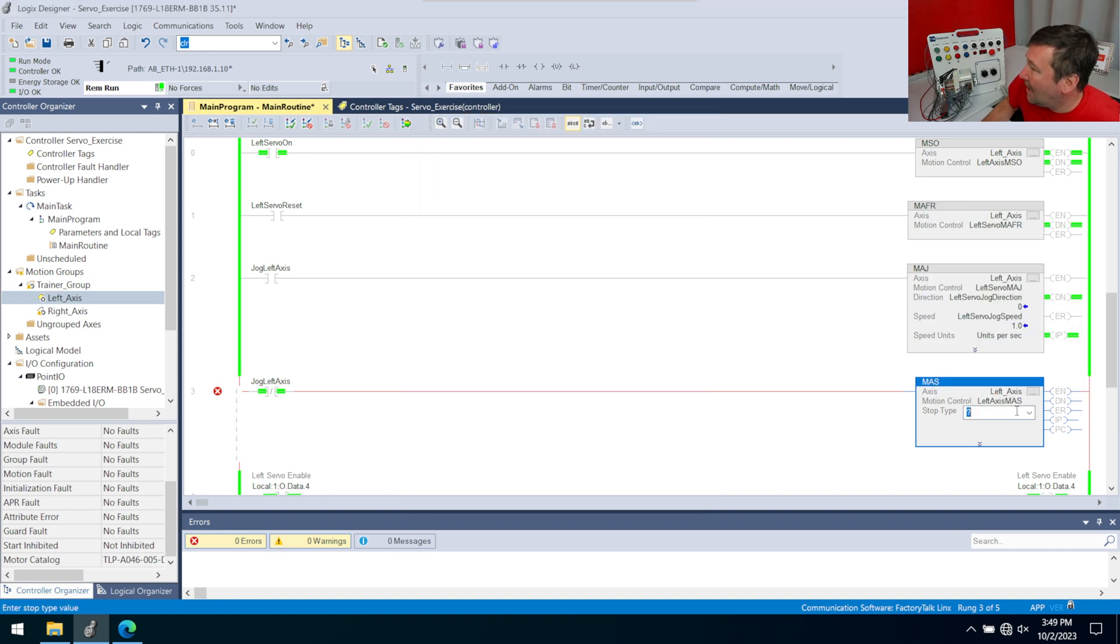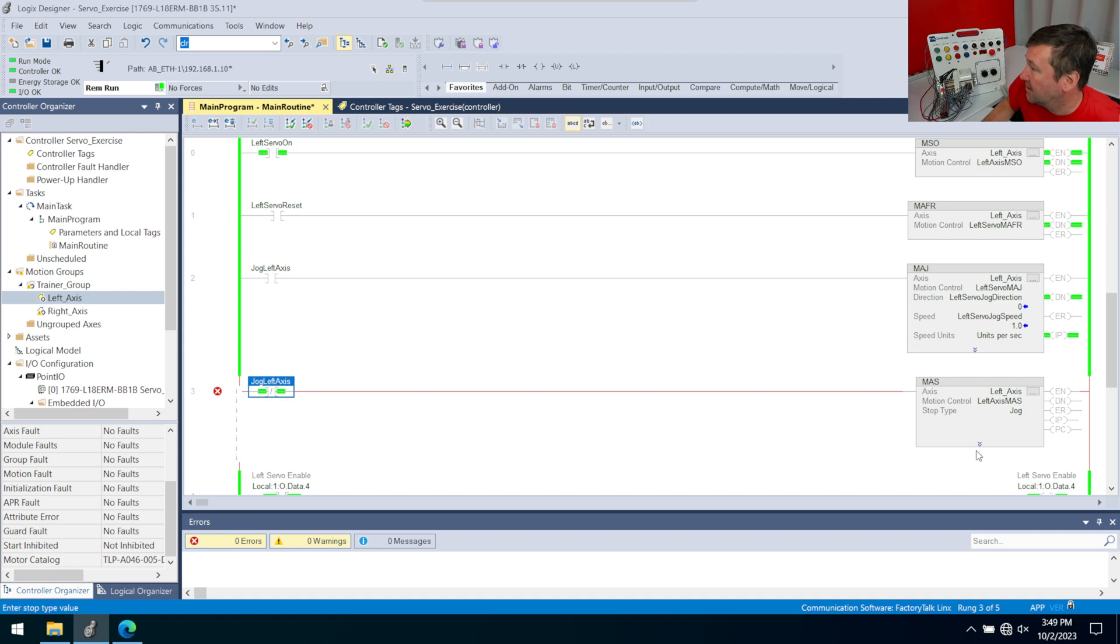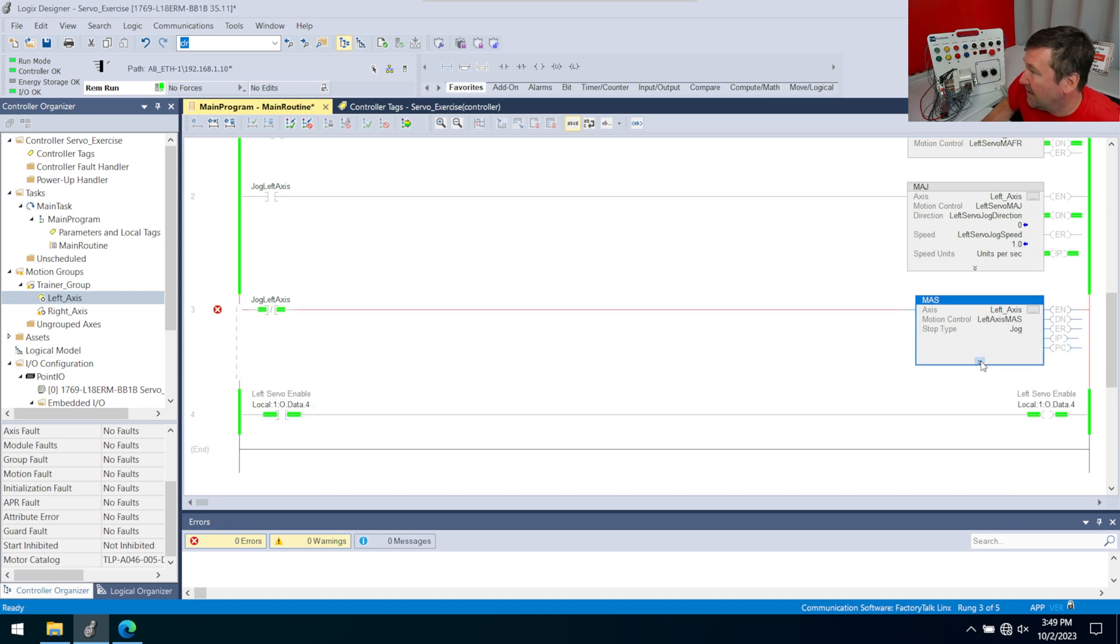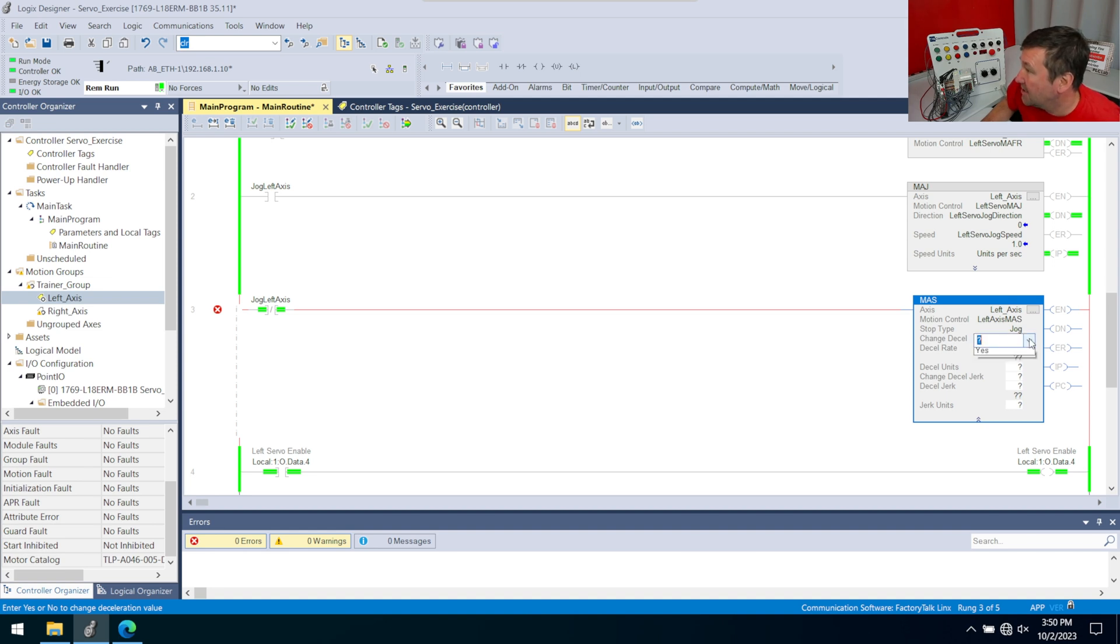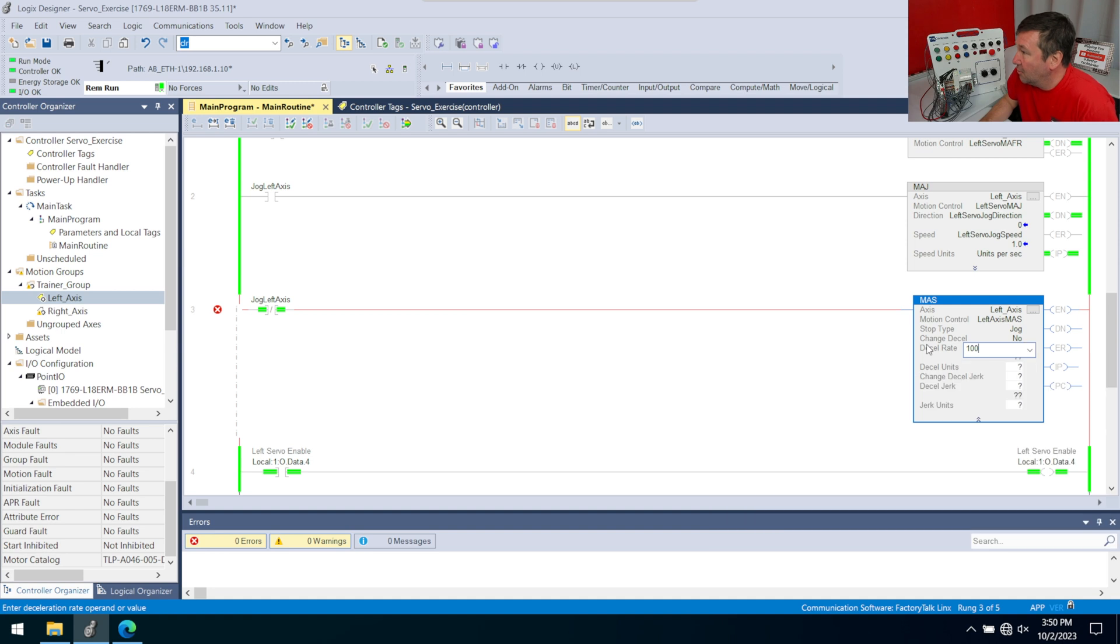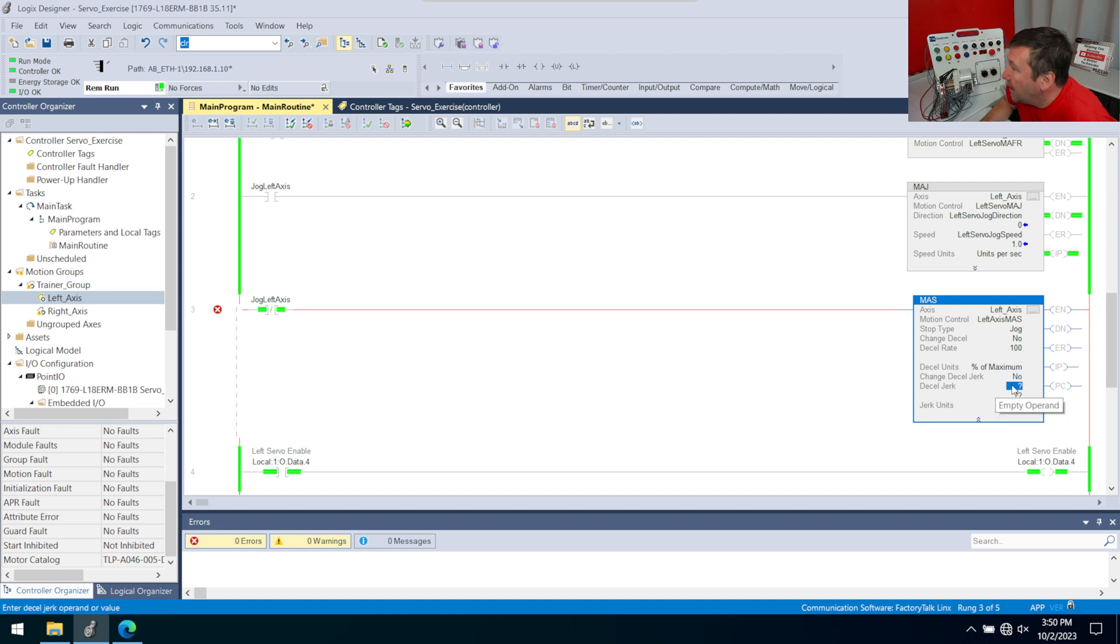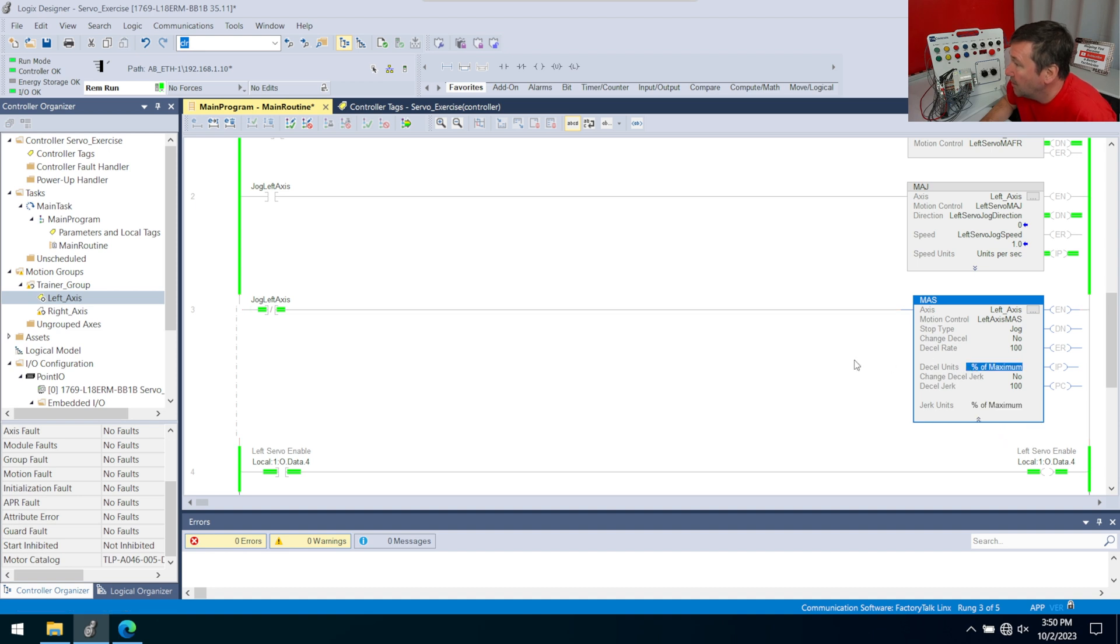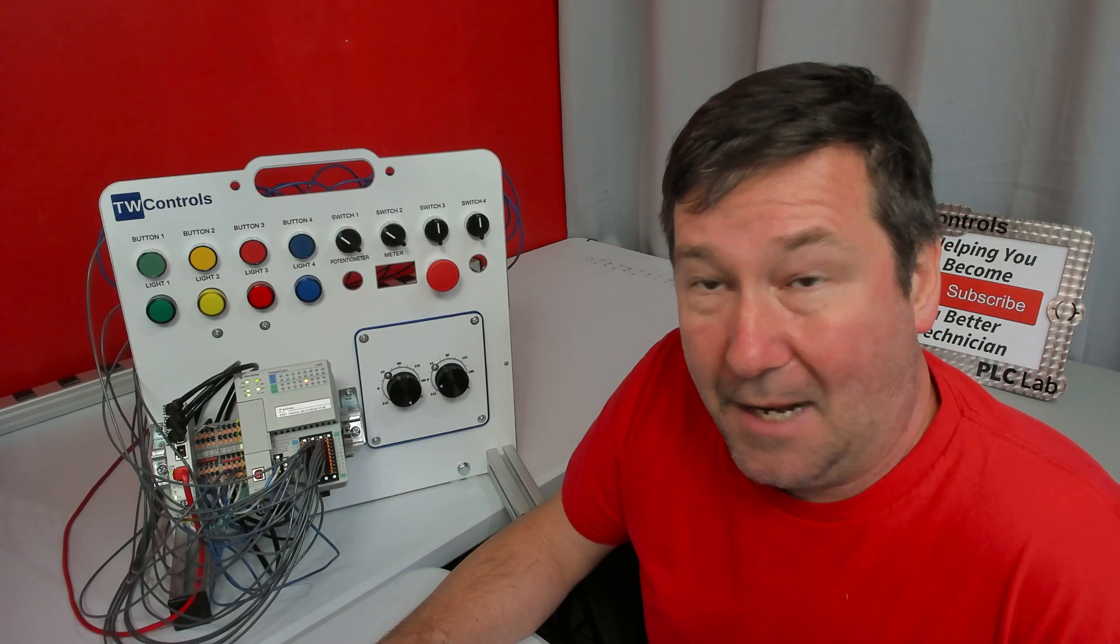Then we have a stop type here. It could be all. In this case, we are stopping a jog, so we're going to stop jogs. We're going to use the jog to do it. We have an arrow here. We still need to hit it because even though it's hidden, we still have to enter this stuff. First, we have change decel. We're not going to change it. So then our decel rate actually doesn't really matter since we're not changing it. So I'm just going to throw 100 in, and my decel units, I'm going to throw percent of max. Then change jerk, we're going to put no. Since we have no, it doesn't matter, but we still have to put something in. So we're going to put 100%.